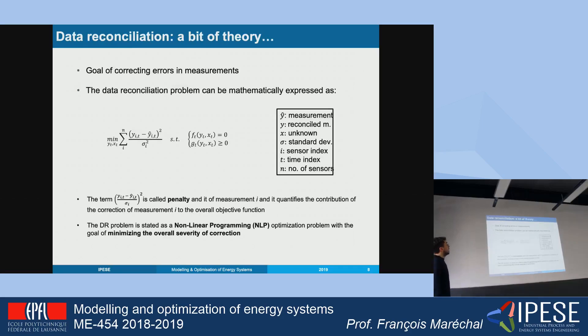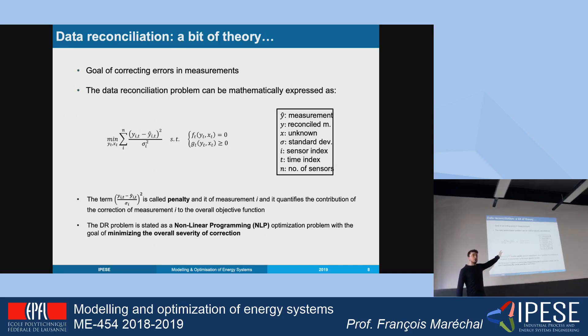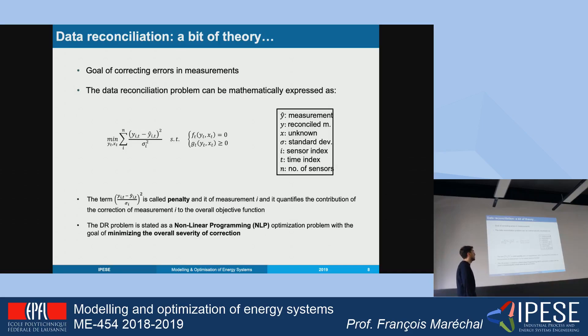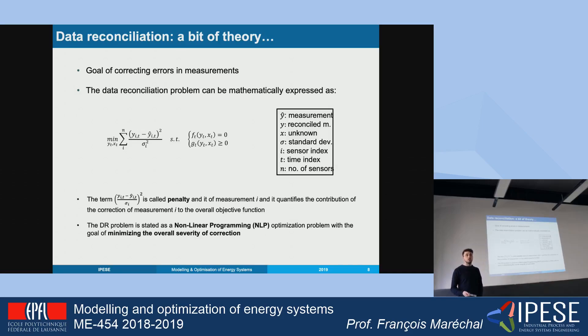A data reconciliation problem is essentially an optimization problem. You have an objective function which is the minimization of the sum of the squared difference between the measured value and the true value — the reconciled value — weighted by the variance (sigma is the standard deviation of the sensor), summed over all sensors. This objective function is constrained by equality and inequality constraints, which are all the equations of your model: mass balances, energy balances, performance equations, etc. The term inside the objective function is called the penalty, because it quantifies the penalty of each sensor.